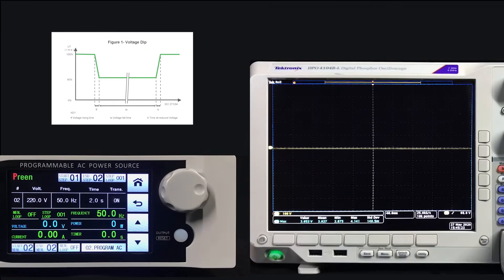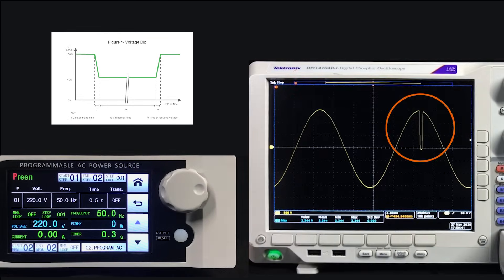From the oscilloscope we can see the voltage drops 100% in a short period of time. The AFV-P series can generate the voltage dip waveform according to our settings.